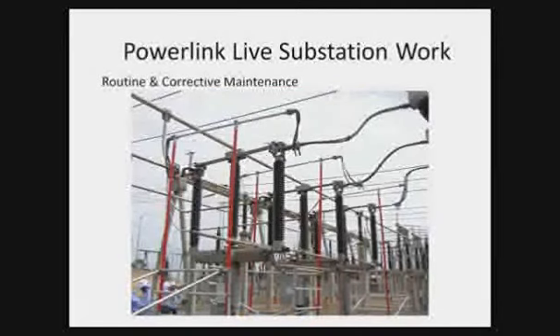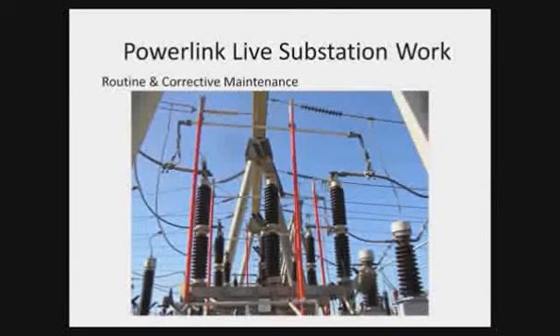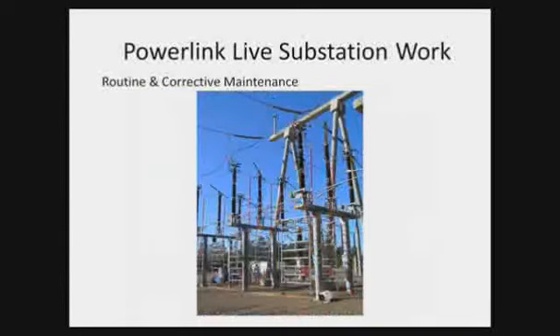Here are some more examples. These are 132 kV disconnectors. You can see the three phases there shunted. The next slide shows that disconnector now opened after it's been shunted, so again it can be maintained. And that's just a bigger version. You can see there that we use aluminium scaffolding to hold our hot sticks in place.